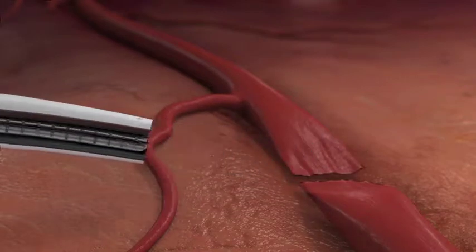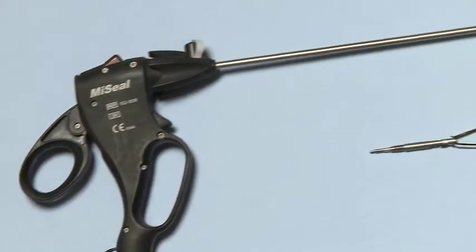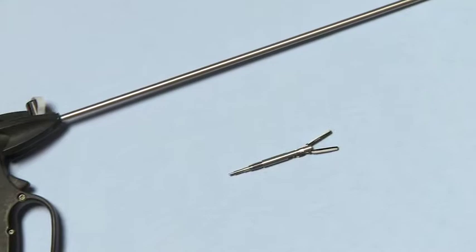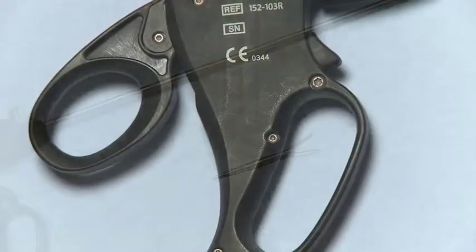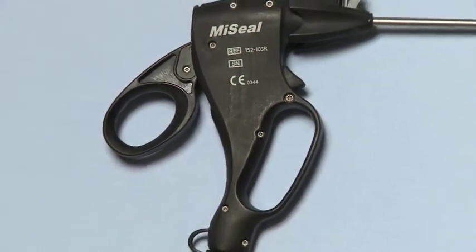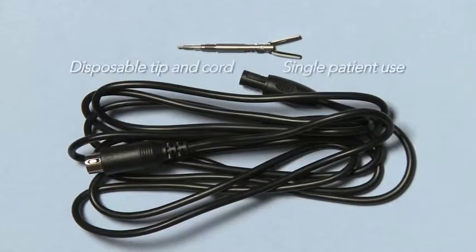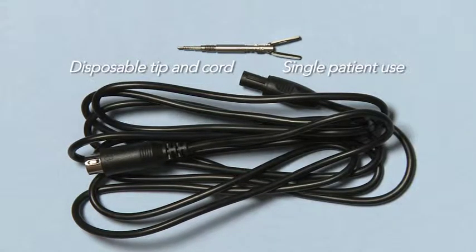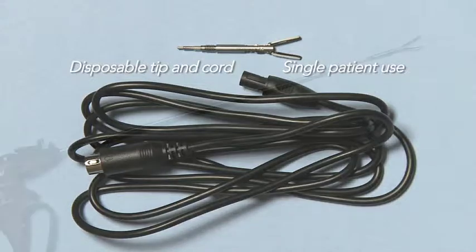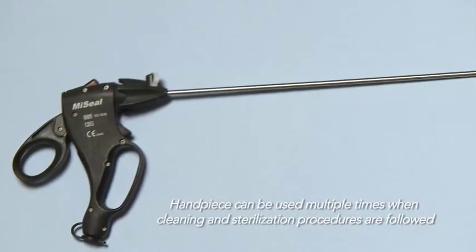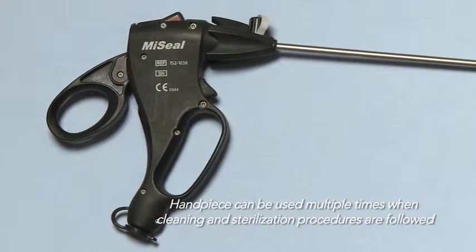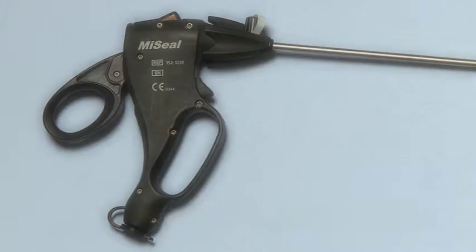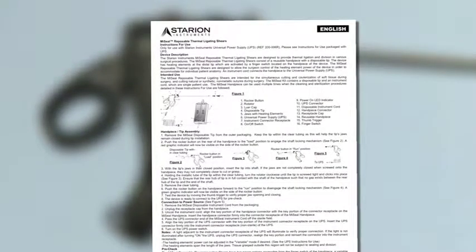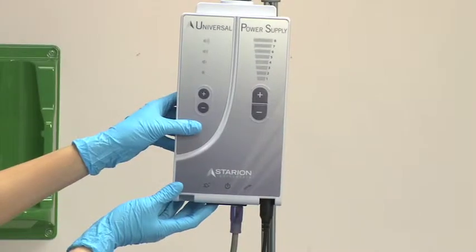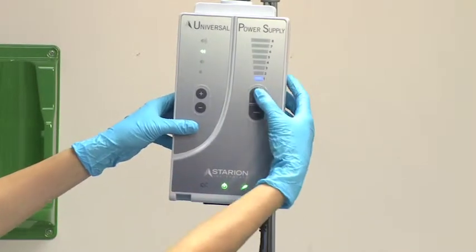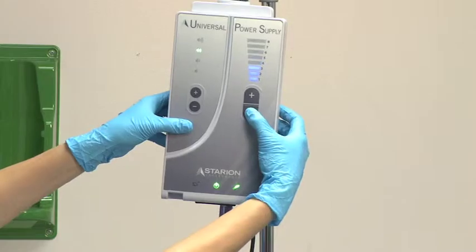Because Miseal is reposable, it offers cost-effective, eco-friendly benefits compared to fully disposable devices, as it may reduce the disposal cost of biohazardous waste. The Miseal kit contains a disposable tip and cord, which are single-patient use. The Miseal handpiece can be used multiple times when the cleaning and sterilization procedures detailed in these instructions for use are followed. The system is compatible with the compact 3-pound universal power supply.